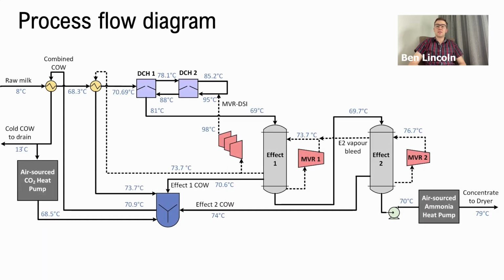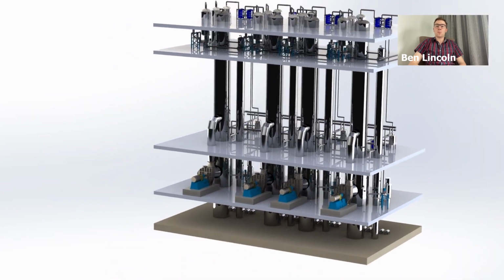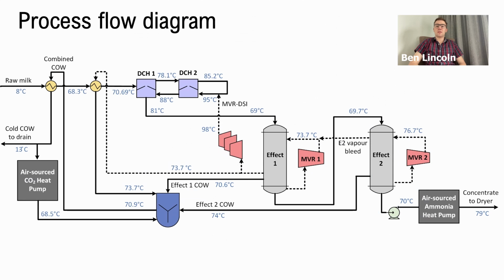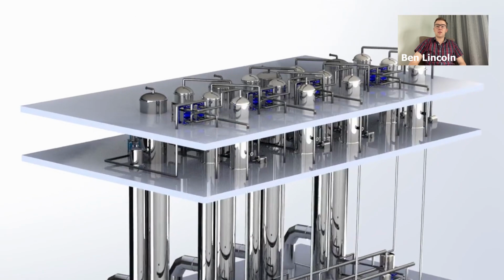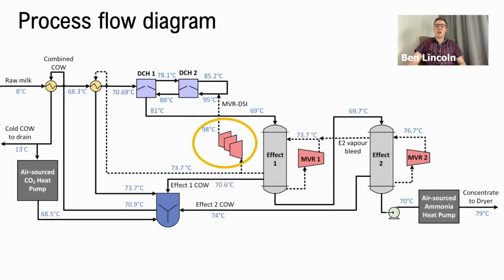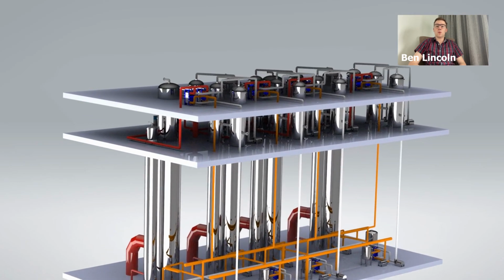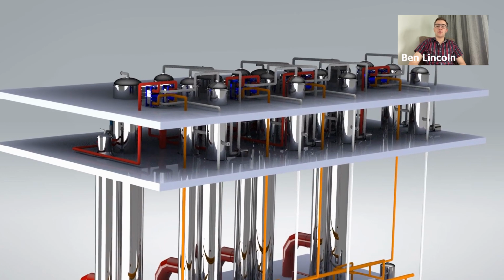The culmination of these considerations was incorporated in our final design of an electric milk evaporator system, which features an optimized preheating process design which uses minimal electricity and will be easy to clean and operate. The key features of this process design include the use of 2 direct contact heaters for fast heat transfer and process simplicity, as well as a 3-stage vapor fan that upgrades excess vapor in order to substitute steam that would have been traditionally supplied from a fossil fuel boiler.